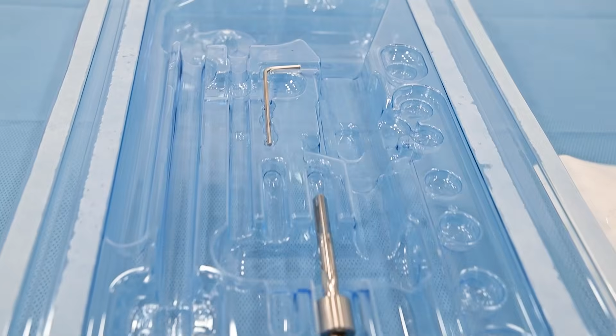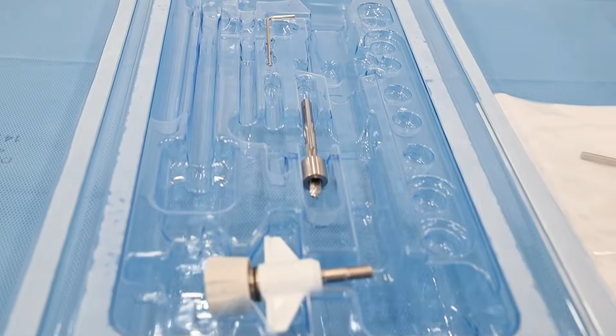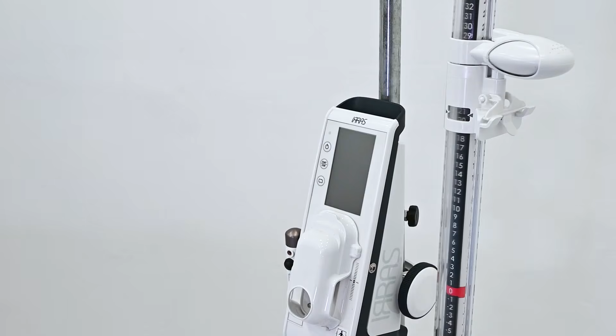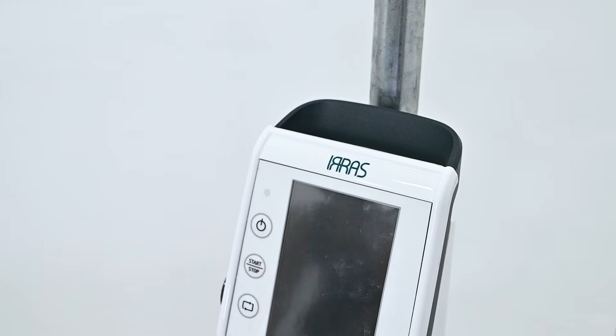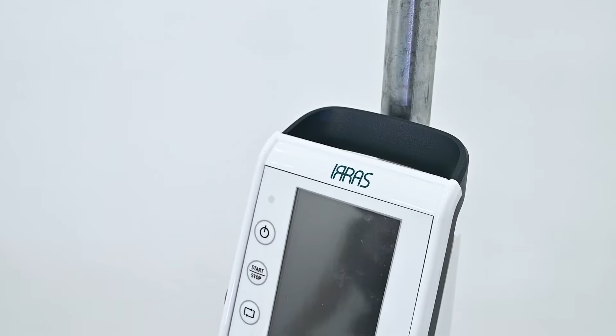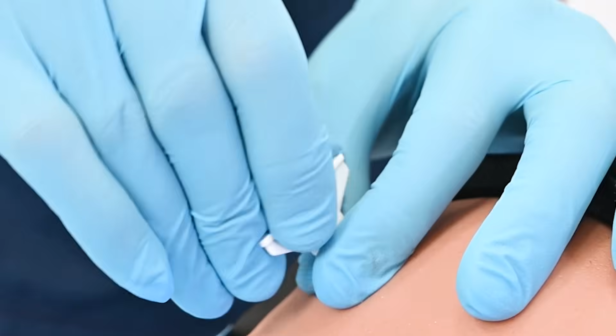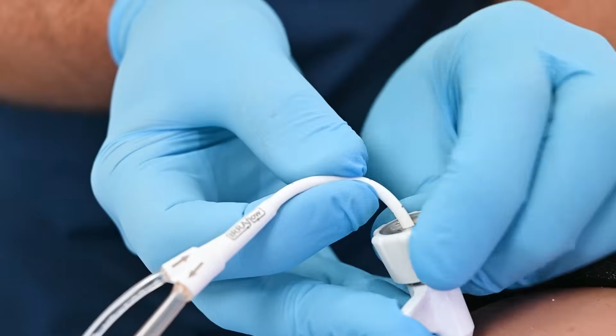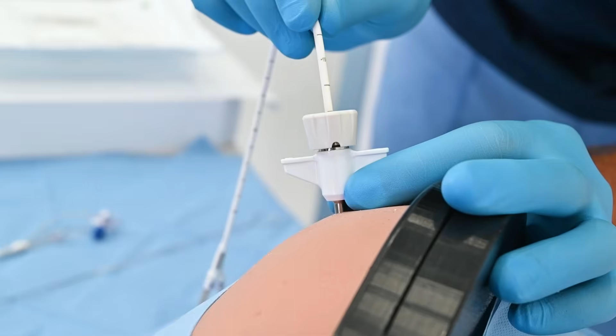The IRRAflow cranial access bolt is a single-lumen cranial access device designed for use with the IRRAflow dual-lumen catheter. It is indicated when ICP monitoring is required and for externally draining intracranial fluid as a means of reducing ICP in patients where an external drainage monitoring system is needed. The use of the bolt is at the discretion of the healthcare professional to secure the catheter to the patient's skull while providing a sealed connection that prevents unintentional fluid leakage or entry.